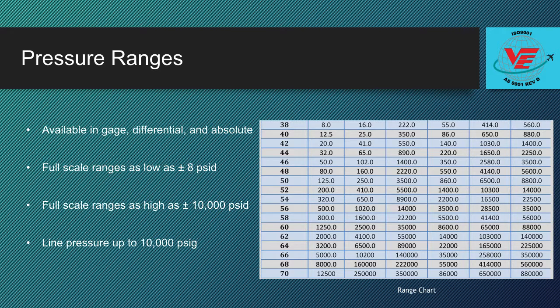The P365 is available in a wide variety of pressure ranges, especially low differential pressure ranges, while operating at up to 10,000 psig of static pressure. The P365 can be ordered with differential and gauge pressures as low as 0 to plus or minus 8 psi differential. With an accuracy of 0.5% and an optional accuracy of 0.25%, the P365 is ideal for measurement of very low differential pressures at high static pressures.